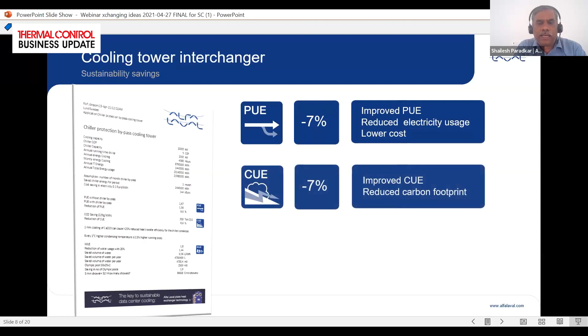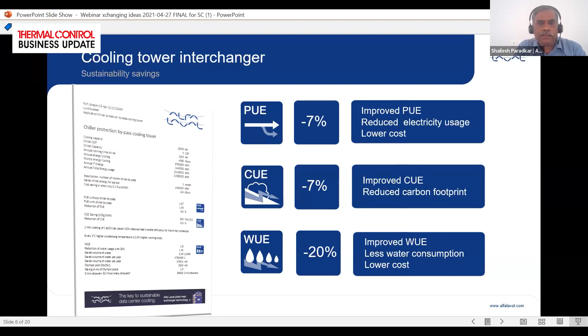That's a benefit. As your condenser is less fouled, you also save on water usage, because if your chiller condenser is fouled, then you need to pass more water through the condenser to achieve a certain capacity. All these losses are not even taken into account, but simply by turning off the chiller for a month or so, it gives a great benefit, particularly in cities like Pune or Bengaluru. I think we have suitable climatic conditions, and this application can save energy for the data center.